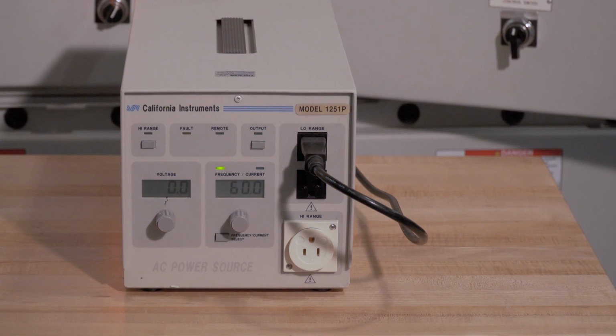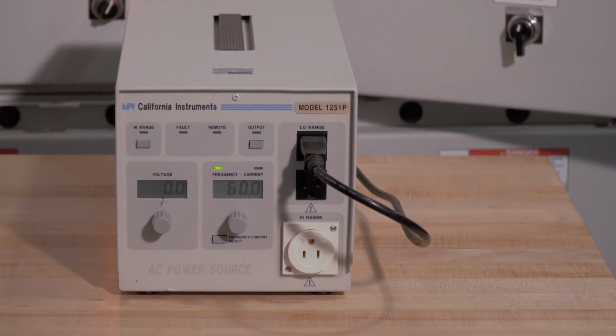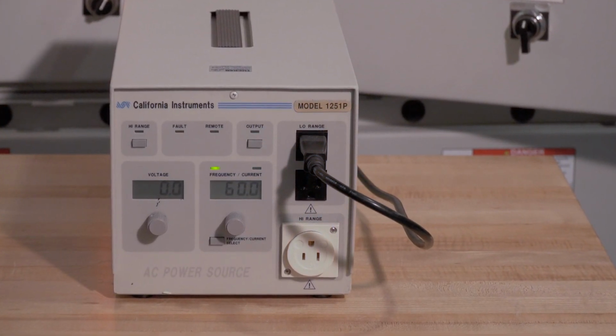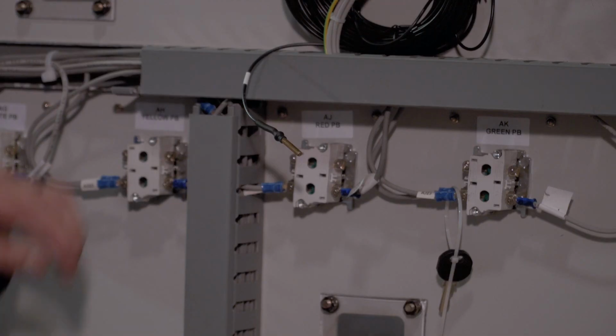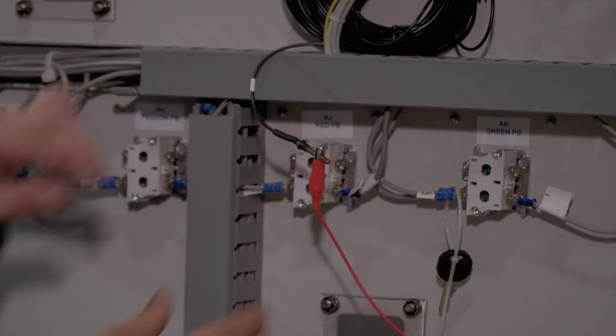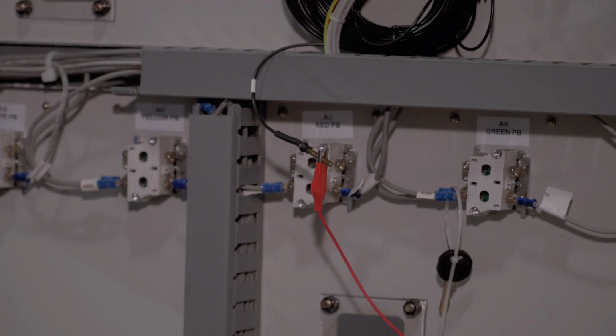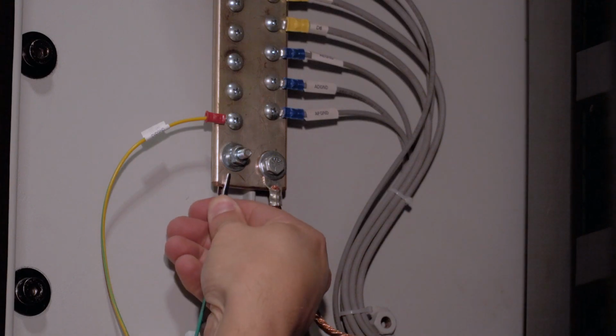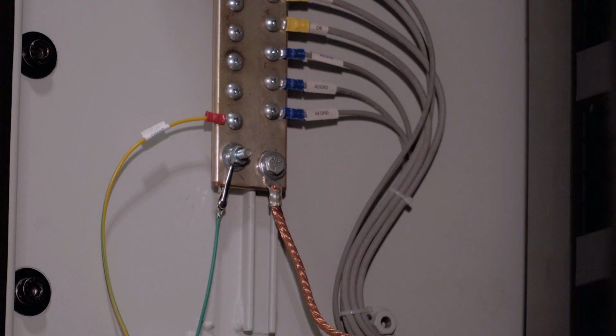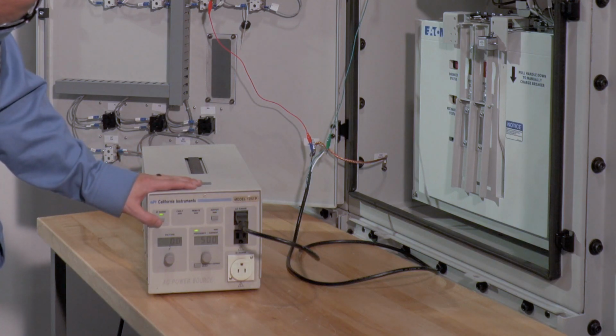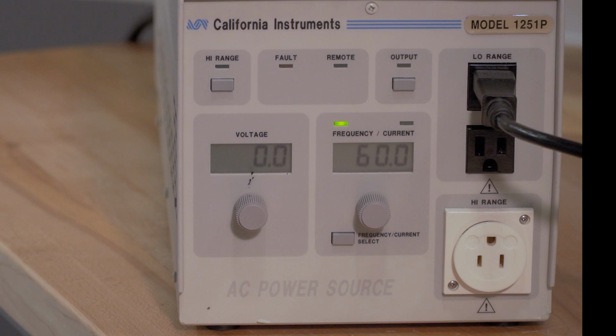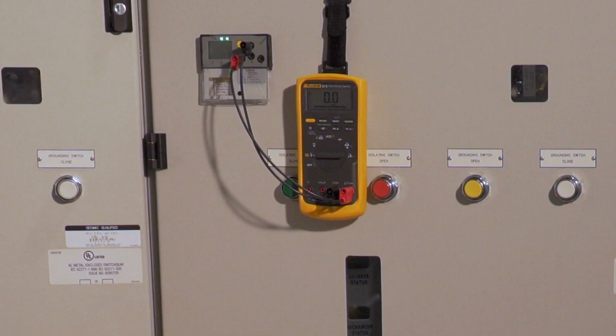To demonstrate this first interlock, we will simulate medium voltage using a low voltage power supply. I will connect the red voltage lead to the VDS voltage lead. I will now connect the green voltage lead to the switchgear ground bus. I will turn on the low voltage power supply. You can see that there is no voltage at this time, and that it is confirmed by the Fluke meter, which is connected to the VDS system.